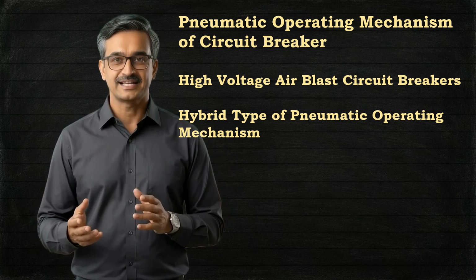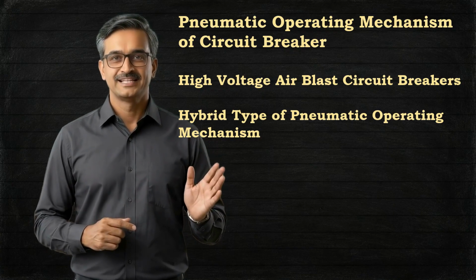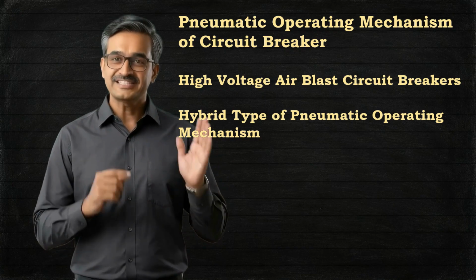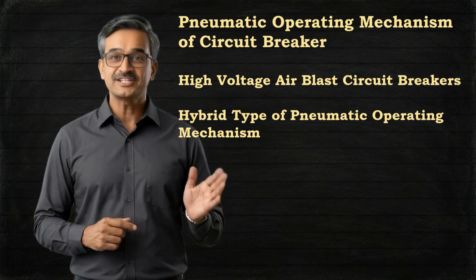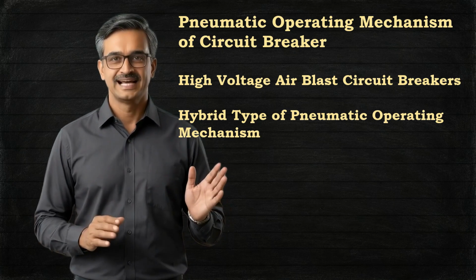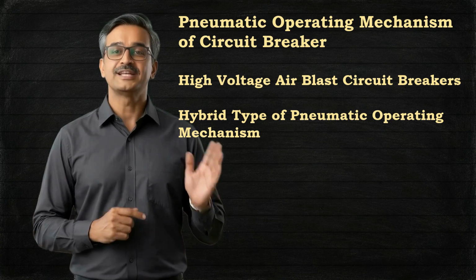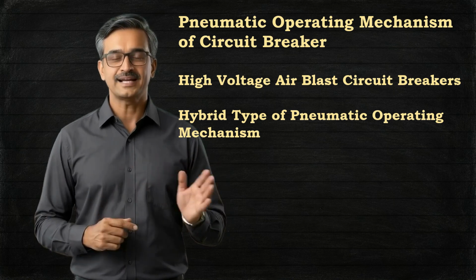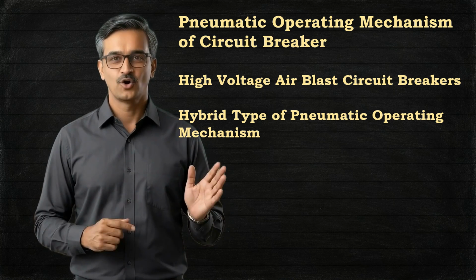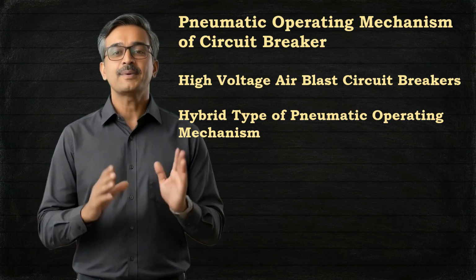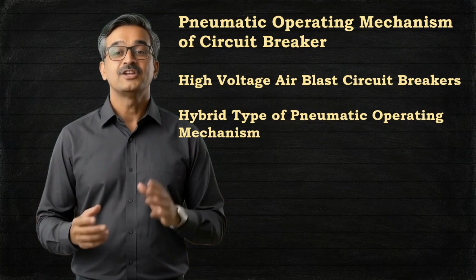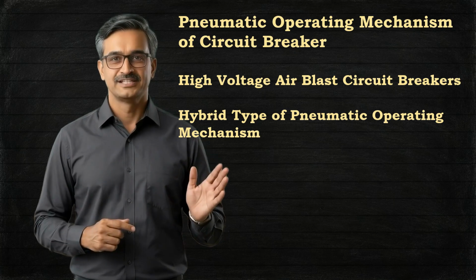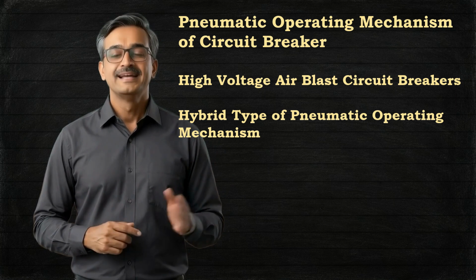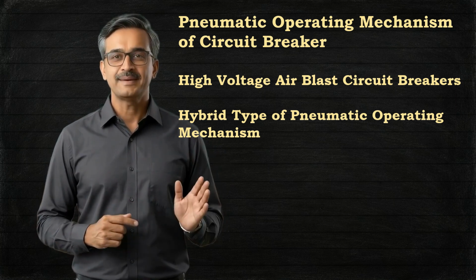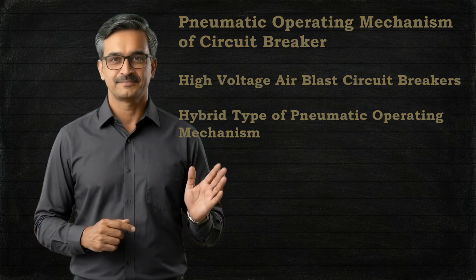That means it is basically a spring-spring mechanism. The only difference is that instead of using a charging motor, compressed air is used to charge the closing spring. That is why it is called a hybrid pneumatic operating mechanism of a circuit breaker. Some manufacturers of SF6 circuit breakers use this hybrid technology. Hope you got a basic idea of the pneumatic operating mechanism of a circuit breaker.